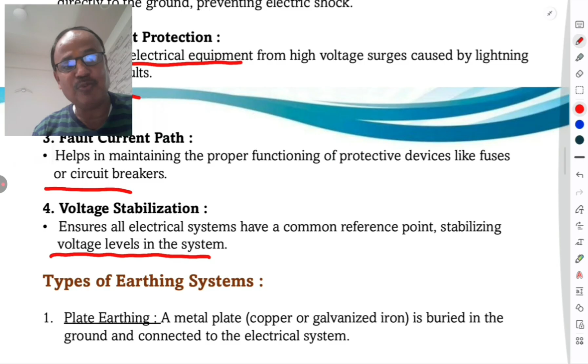Now we discuss the types of earthing systems. First is plate earthing - a metal plate, copper or GI (galvanized iron), is buried in the ground and connected to the electrical system. Rod earthing - a metal rod or pipe is driven into the ground to provide an earth connection. Strip earthing - a metal strip, copper or steel, is buried in a trench to dissipate the fault current. Earth electrode earthing uses an electrode to establish a direct connection to the ground.